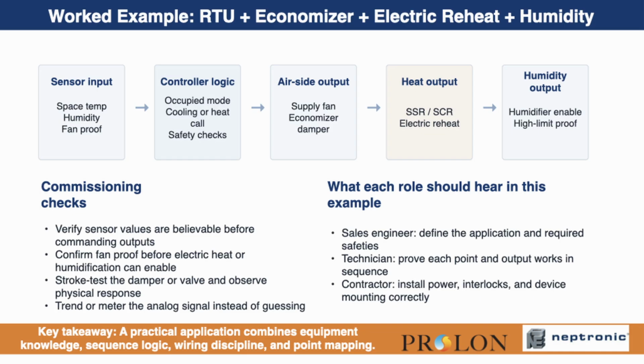This is a good example because it shows that field success depends on combining equipment understanding, sequence logic, wiring knowledge, and point mapping. Let us walk through the example from sensor input to humidity output. The sensor inputs may include space temperature, discharge temperature, space humidity, and fan proof.